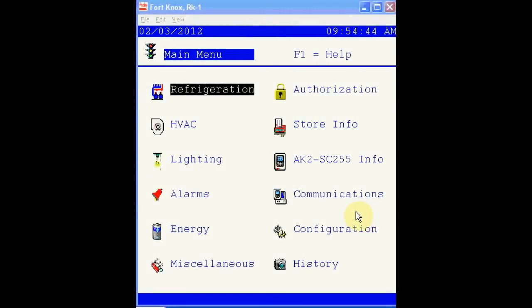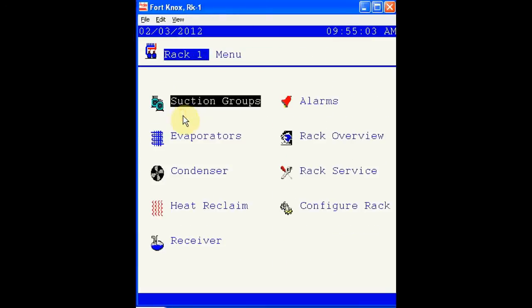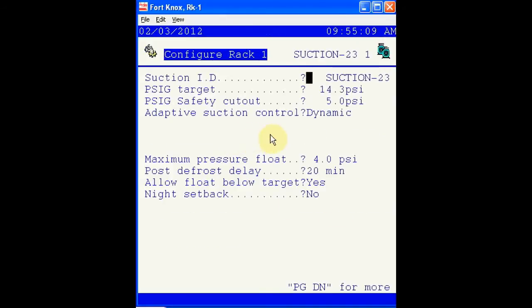Let's look at another feature of the AK2-SC255 called dynamic suction float. This option allows the rack to float the suction pressure up when specific cases have reached their target. It's called dynamic because it can switch between several cases. To see the settings, navigate to Configure Rack and Suction Info. The suction ID is listed at the top. Below that we'll find PSIG target of 14.3 pounds. This is the base target for this suction group. This group is allowed to float a maximum of 4 pounds.